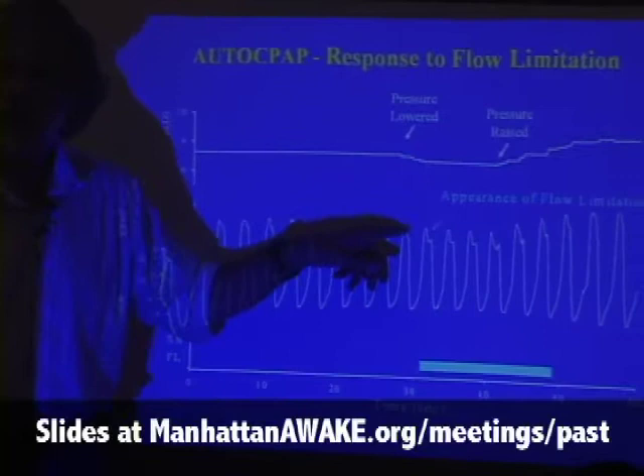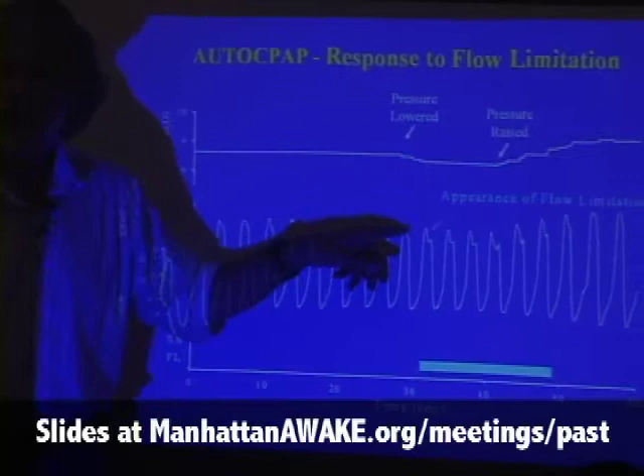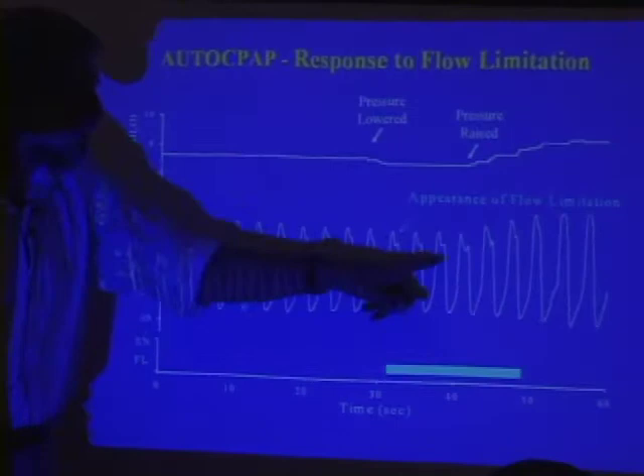The machine decides everything is good by looking at the shape of the breathing. If it's round, that's good. If it's flat, that's bad. What it does is lower the CPAP by a tiny amount, sees a change from round to flat, and goes back up — doing this almost continuously. We found out we were waking people up, very much like the elbow in the ribs analogy. So we added a wait time of five minutes when we're in a good place before testing again, though there was much jockeying about how long to wait.